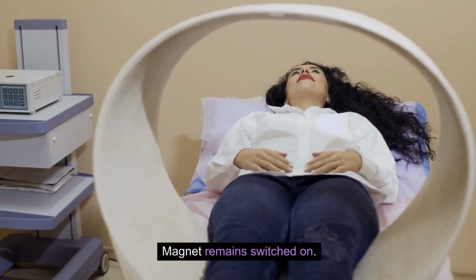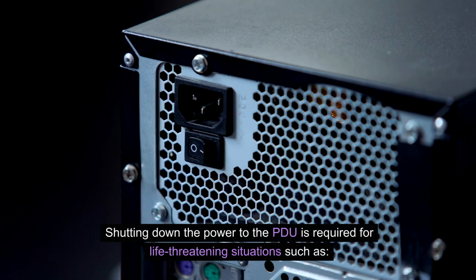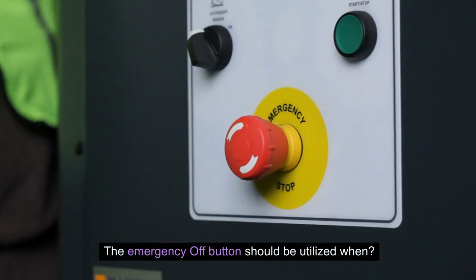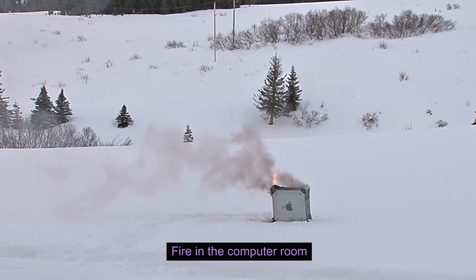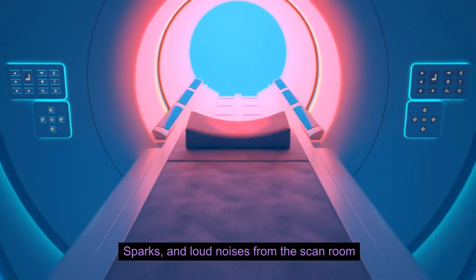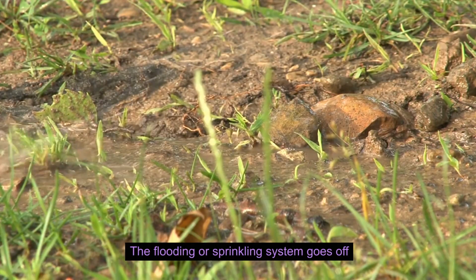The magnet remains switched on. Shutting down the power to the PDU is required for life-threatening situations. Question: the emergency off button should be utilized when? Fire in the computer room, sparks and loud noises from the scan room, or the flooding or sprinkling system goes off.